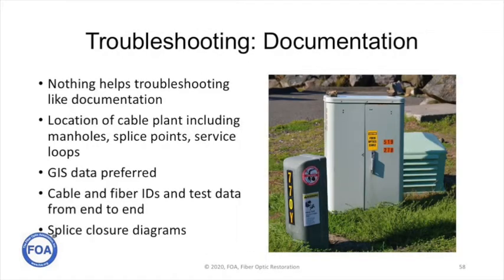Troubleshooting the cable plant depends on having good documentation. You need to know how long each fiber link is, where splices are, and the location of pedestals. You need GIS data that tells you where everything is, and you need cable and fiber IDs and test data from end to end so you can actually do your troubleshooting.